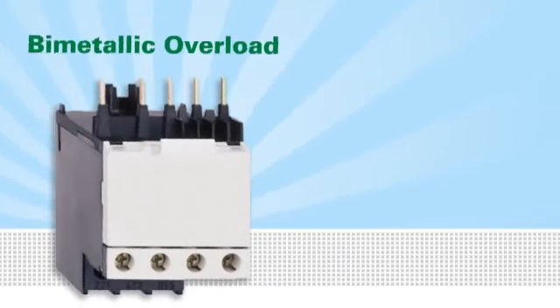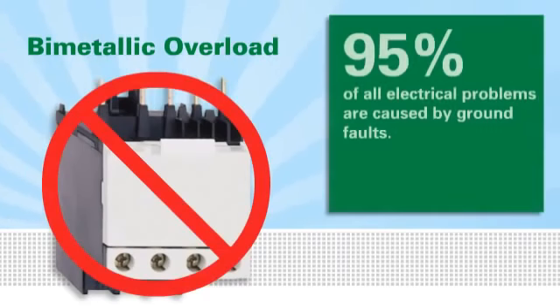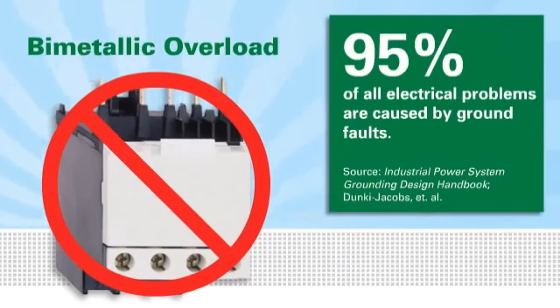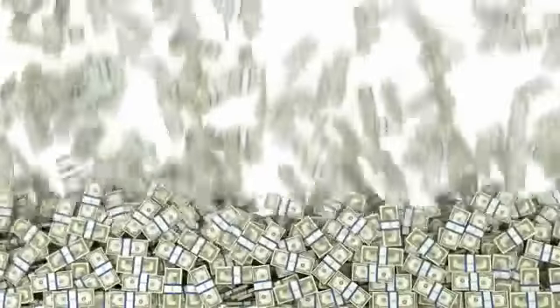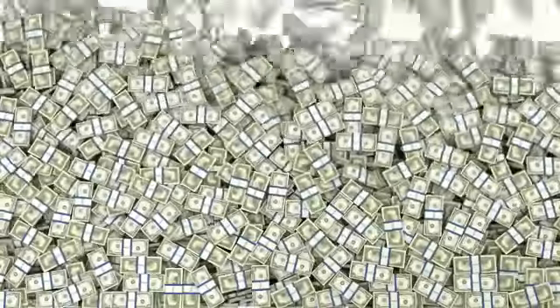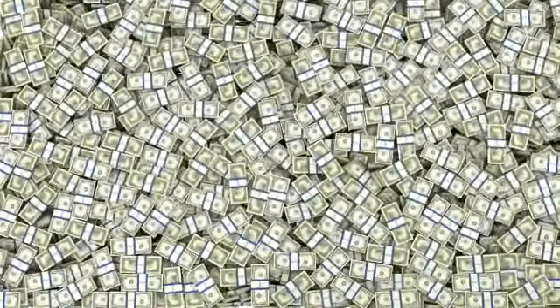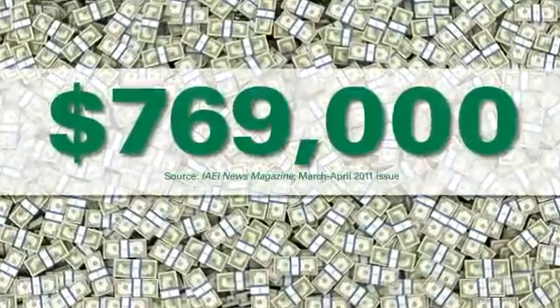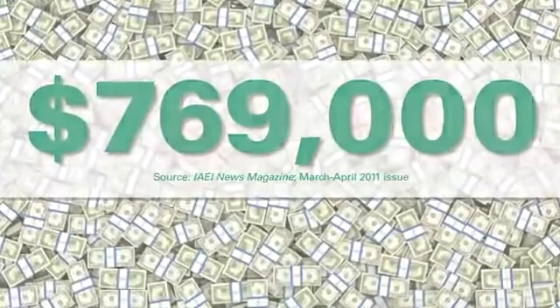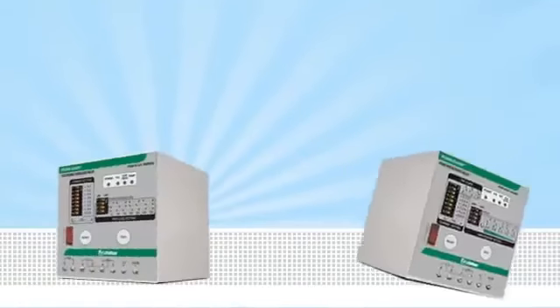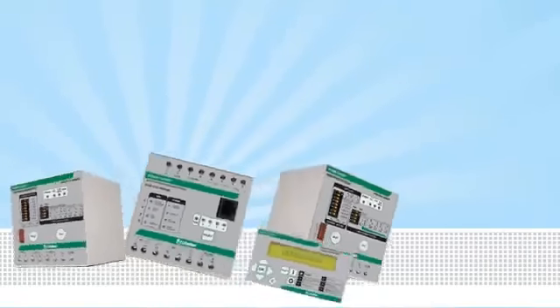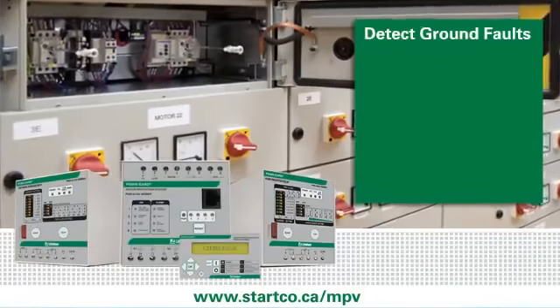Conventional thermal overloads are also unable to detect ground faults, which cause an estimated 95% of all electrical problems. A leading insurance company reports that typical manufacturing claims resulting from electrical problems end up costing approximately $769,000. Claims that might have been avoided with the Littelfuse motor protection relays, which can detect ground faults, alert operators, and minimize equipment damage.